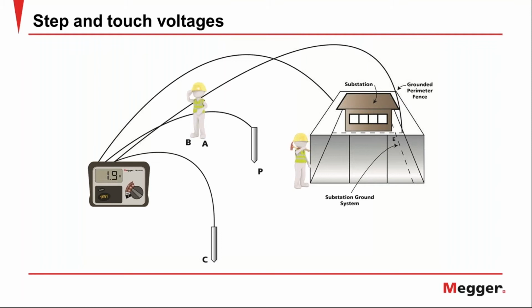And then your step potential will just be 2 probes about 3 feet apart, like we see B and A there. And so what you're doing is measuring the resistance between the points of someone touching the fence with their foot maybe 3 feet away from the fence, and someone walking by in 3-foot strides. You take the resistance measurement off your tester, and you would get the maximum fault current that the substation can experience. And if you multiply them out in simple Ohm's law to give the voltage, you don't want the voltage to be any more than 50 volts.